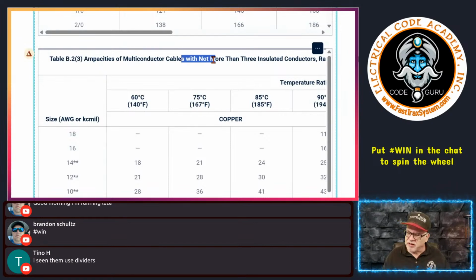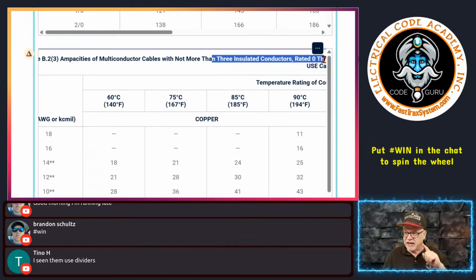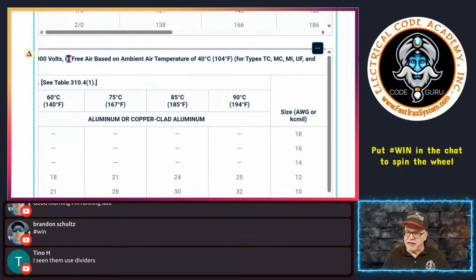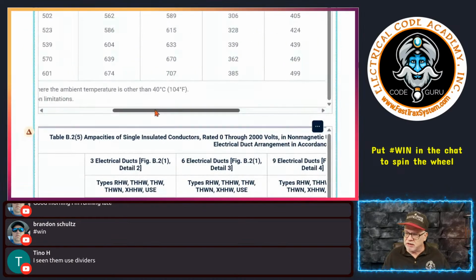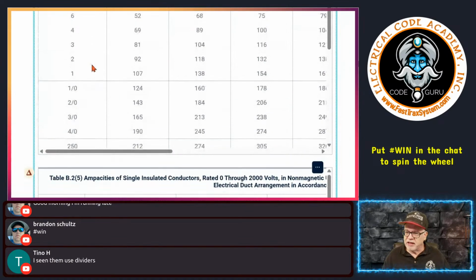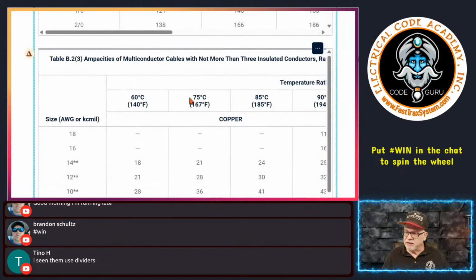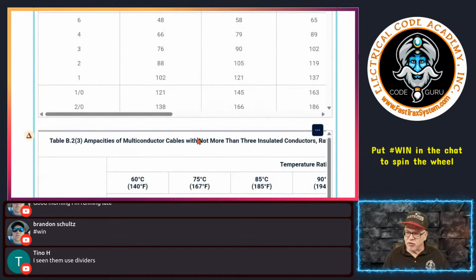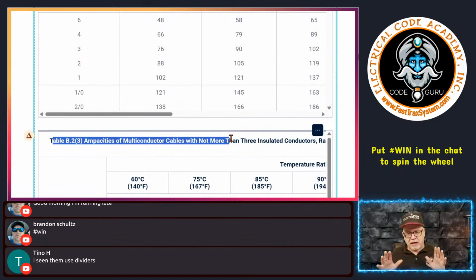But you see how it talks about where it's not more than three, not three current carrying conductors. It says not more than three insulated conductors. And it talks about based on free air, based on 40 degrees C, and then based on these types of cables. I want you to notice something. If I go down and look at the ampacities, you'll see, for example, here under the 75 for copper, you'll see that this is good for 245 for a 4/0, or 3/0 is good for 213, okay? This is based on those conditions. That can only be done by engineering supervision. And this table is just a shortcut based on the Neher-McGrath that the engineer can go to.